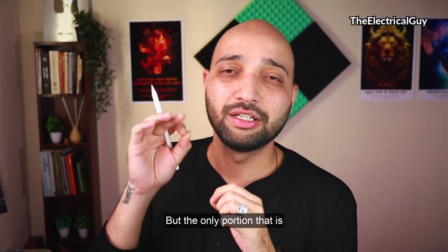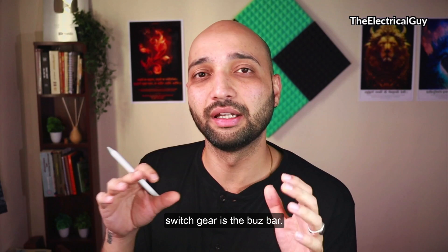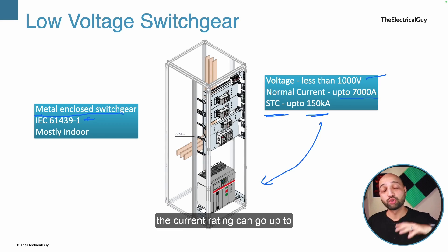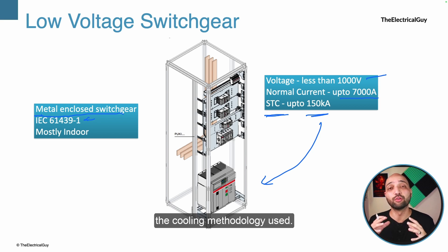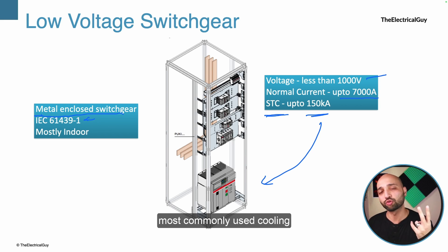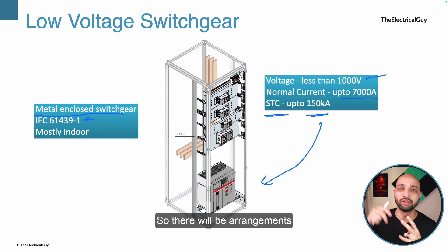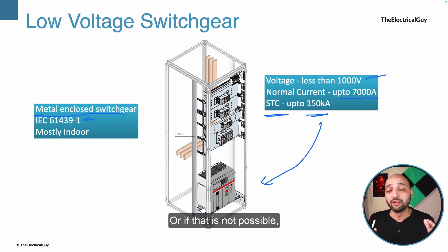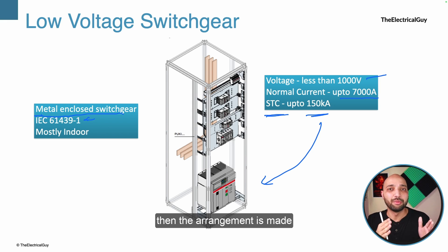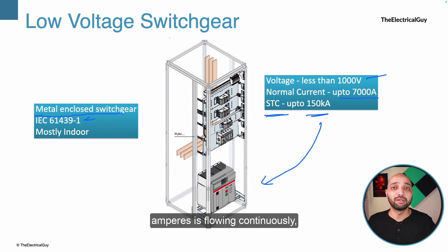The vital area in low voltage switchgear is the bus bar. Since normal current can go up to 7000 amperes, there will be significant heating issues. The cooling methodology is therefore a very focused area. There are two commonly used cooling technologies: natural cooling, where arrangements circulate natural air through the panels to keep temperature within limits, and artificial cooling using fans. With 7000 amperes flowing continuously, it generates a lot of heat not only in the bus bar but across the complete panel.